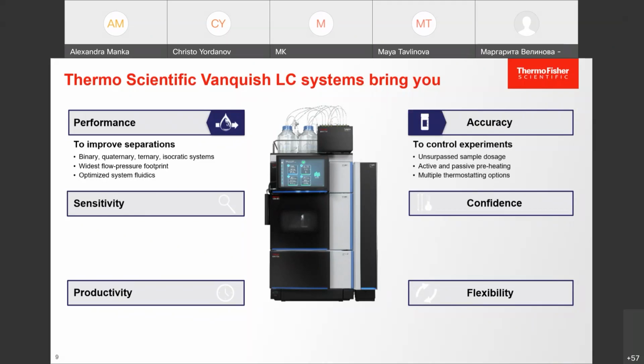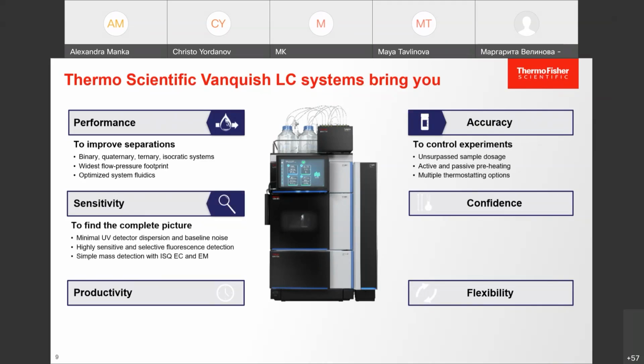In terms of accuracy of the systems, we have an unsurpassed sample dosage with the new autosamplers with the metering devices in there. Then in the column ovens, we offer active and passive preheating, and we have multiple thermostating options within the column ovens. For sensitivity of the systems, we offer different detectors, like UV detectors, which are optimized on dispersion and baseline noise. Then we have a very sensitive fluorescence detector, and as mentioned, the simple mass detection with the ISQ EC and EM.